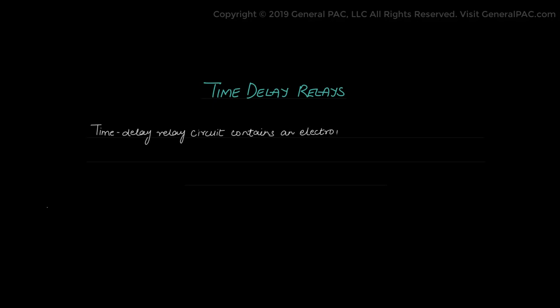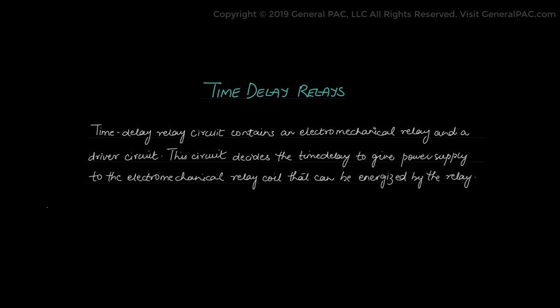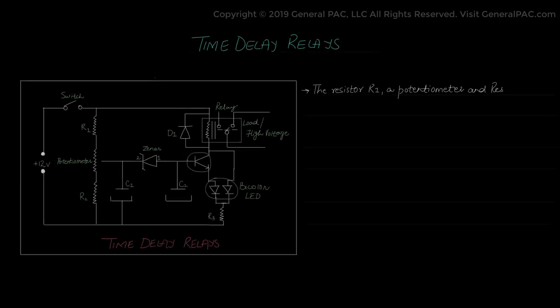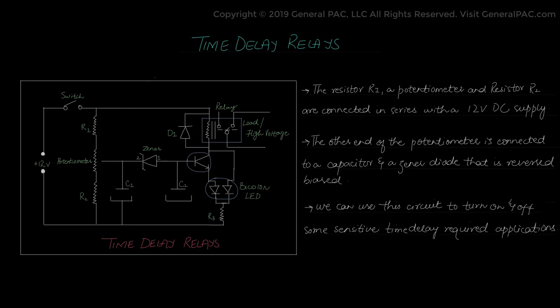The next type of relay is a time delay relay. The time delay circuit contains an electromechanical relay and driver circuit, which decides the time delay to give a power supply so the electromechanical relay coil can be energized. In the working mechanism, there is a resistor R1 and a potentiometer R2 connected in series with a 12V DC input supply, and the other end of the potentiometer is connected to a capacitor and a reverse-biased Zener diode. This circuit can be used to turn on or turn off sensitive time delay required electrical applications.